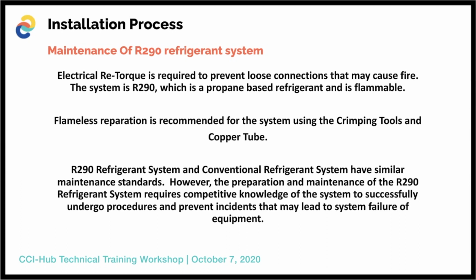The R290 refrigerant system and the conventional refrigerant system have similar maintenance standards. However, the preparation and maintenance of the R290 refrigerant system requires competent knowledge of the system to successfully undergo procedures and prevent incidents that may lead to system failure of the equipment. Another maintenance procedure that we do in our system is proper monitoring of glycol in the system. Cleaning of wire strainers at the pump station must be done at least once a year. Quarterly cleaning of dry cooler fins.